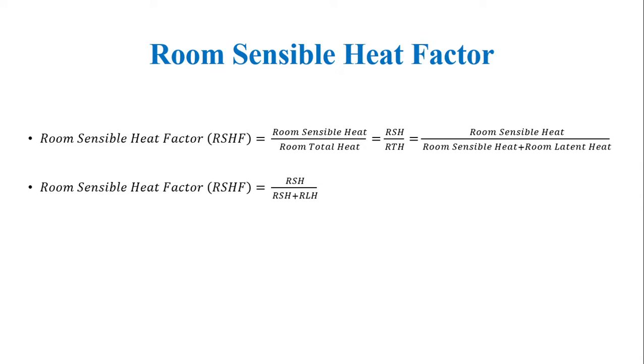The next one is the Room Sensible Heat Factor, RSHF. It is the room sensible heat divided by room total heat. It is similar to SHF — only the word 'room' has been added. Mathematically: RSHF = RSH / (RSH + RLH).